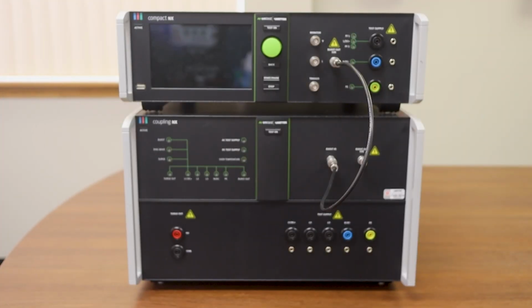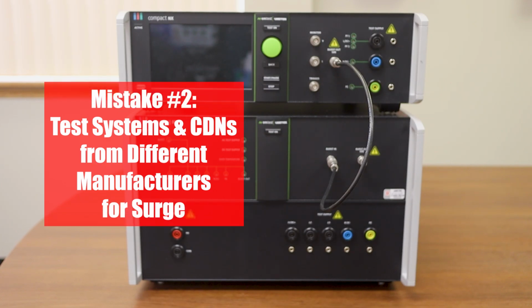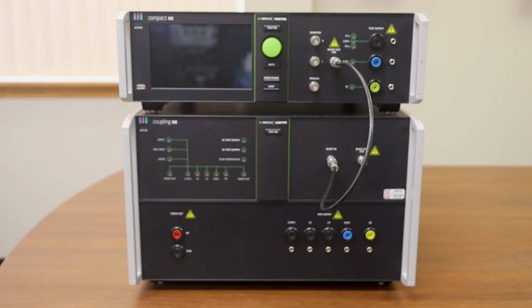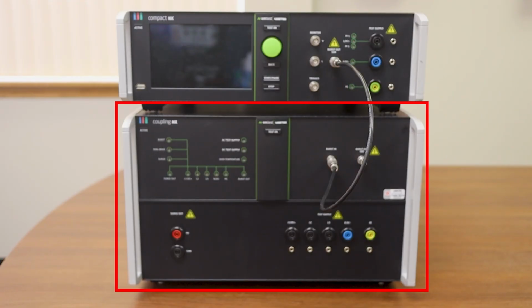The next issue we see is when transient generators and CDNs from different manufacturers are used together for AC power testing where line synchronization is required. IEC 61000-4-5 is a common immunity test and requires line synchronization when testing. We see this most often when surge testing is being conducted on 3-phase applications where external CDNs like the coupling NX7, which you can see below our NX5, are used.